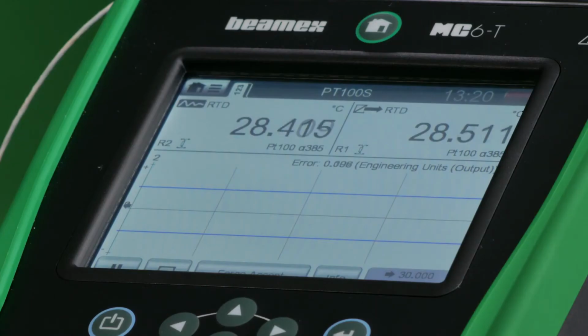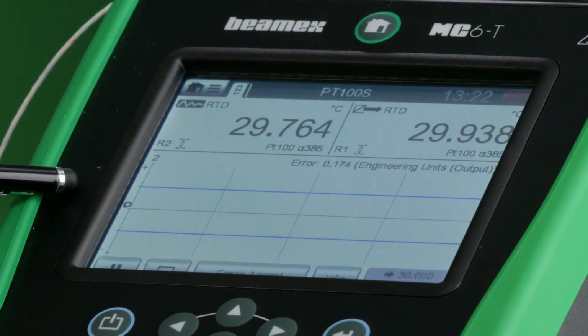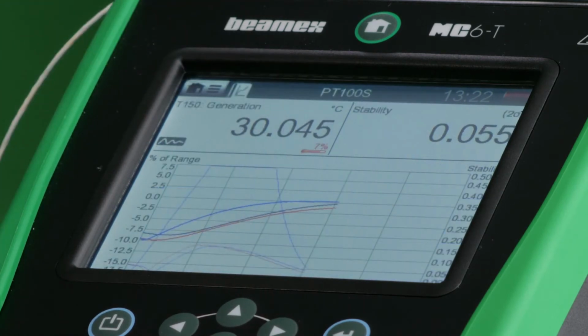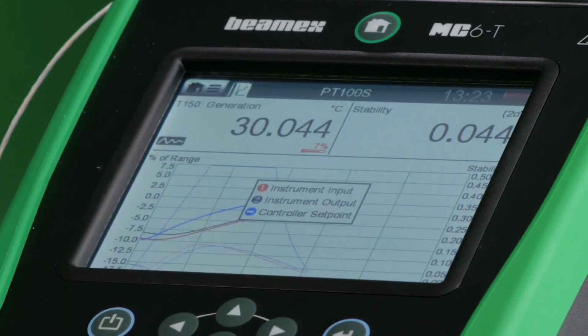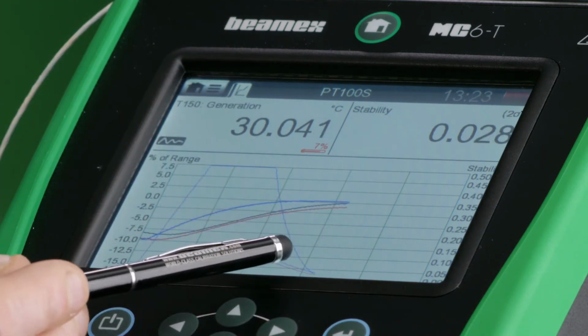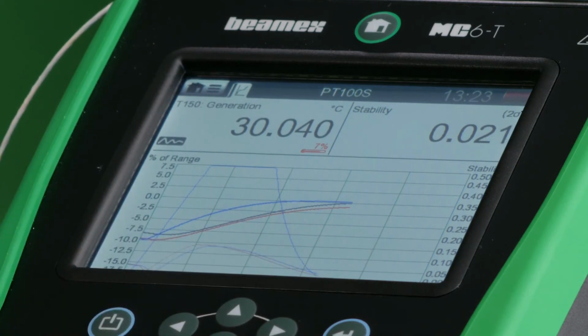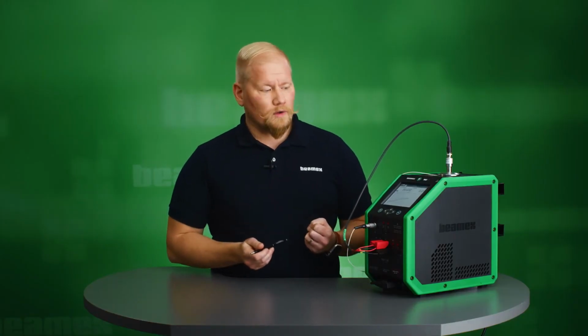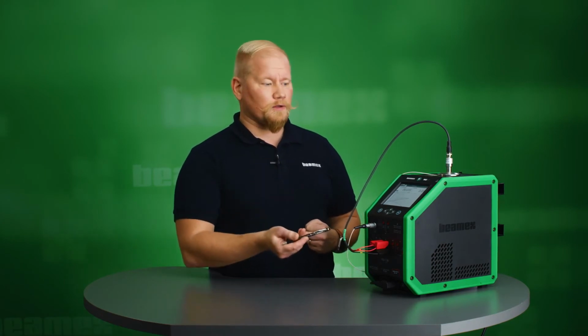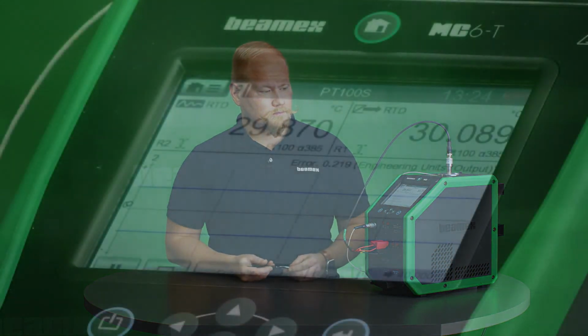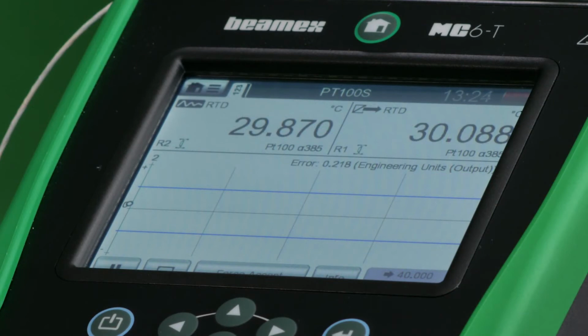This is going to document the results, meaning I don't have to use a pen and paper to document manually, so I'm eliminating the human error in this phase. Now we are getting close to reaching the first set point of 30 degrees Celsius, and I can toggle to my graphical view, seeing my different input and output signals as temperature, and also the thinner line indicating my stability for each signal. When I get to a low enough point, the dry block will automatically record a set point, take the data, and give the instructions for the next set point. Now the MC6-T has reached its first set point.